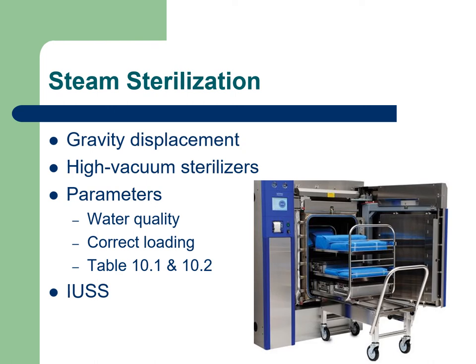If you look on page 197, there's table 10.1 and 10.2. Table 10.1 goes over the parameters for gravity displacement steam sterilization, different exposure times, and how long they have to dry. It addresses exposure times at 250 degrees, 270 degrees, and 275 degrees, so you can look at those at your leisure. The one below that is the dynamic air removal, or pre-vac, steam sterilization. Notice that gravity displacement takes longer than pre-vac, and pre-vac does not have a 250 degree Fahrenheit setting.